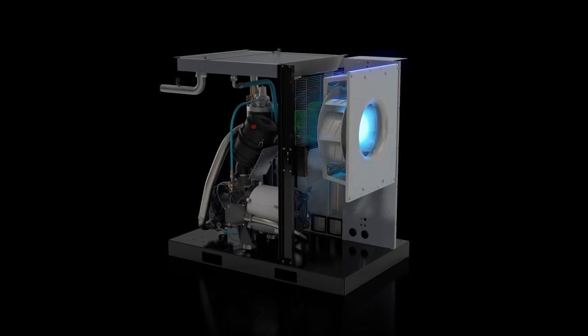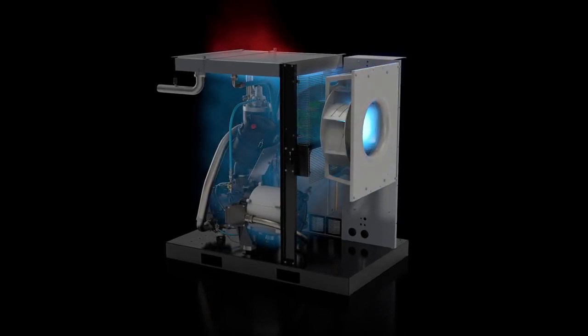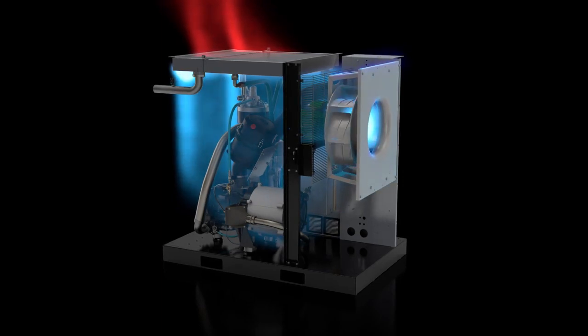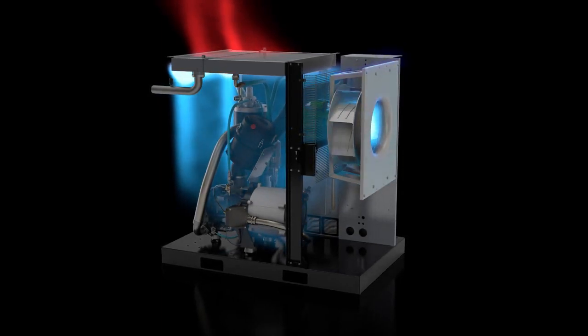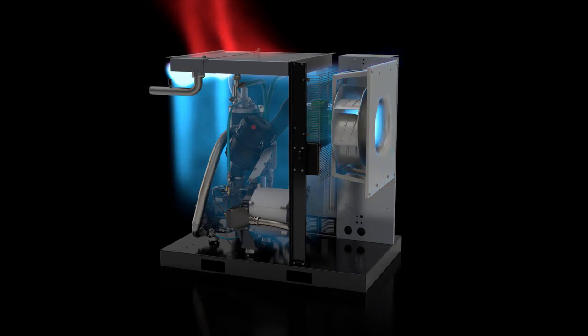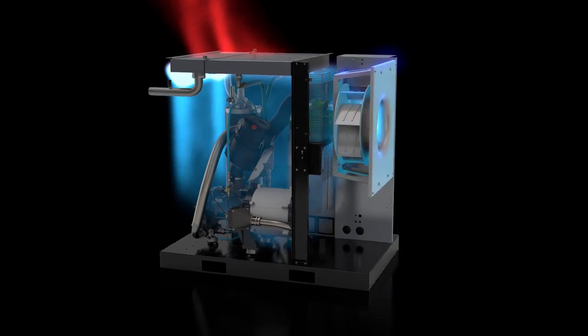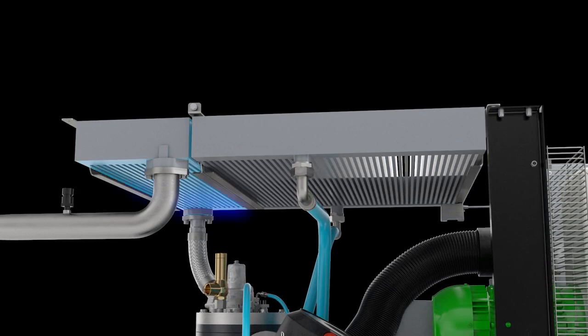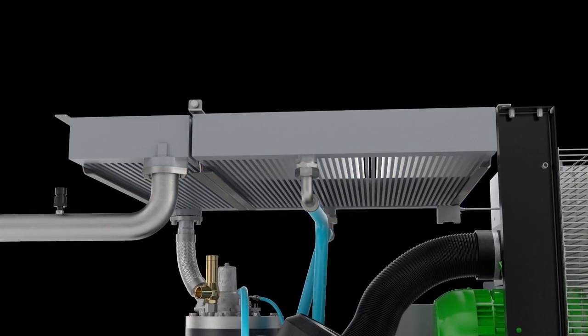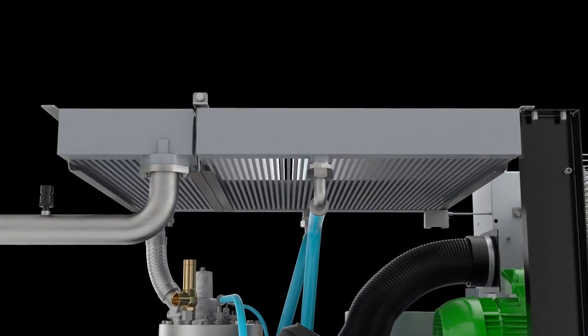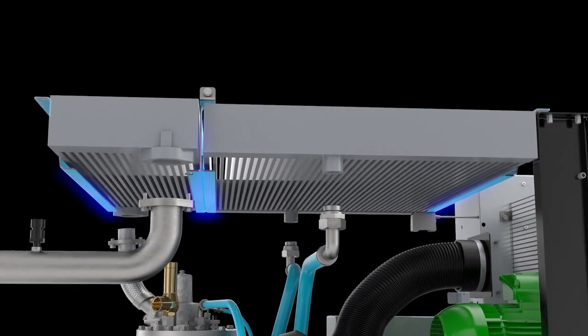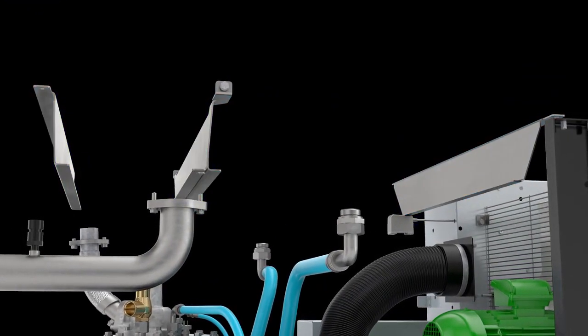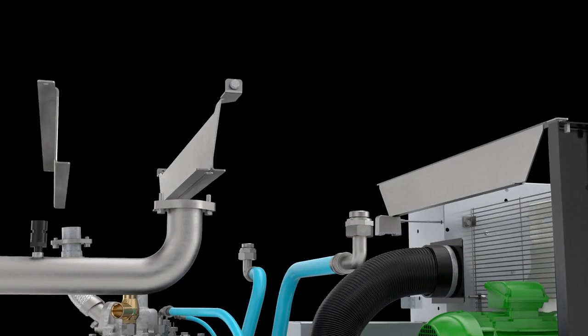The energy-efficient radial fan provides optimal cooling air at a low noise level. Being positioned strategically smart at the side of the compressor, the full cooler surface area can be utilized for optimal cooling and reliability. Two separate cooler blocks, one for air and one for oil, are used to reduce the risk of thermal shocks and increase reliability. The coolers are mounted on gliding rails and can be easily dragged out and cleaned, making service a one-person job.